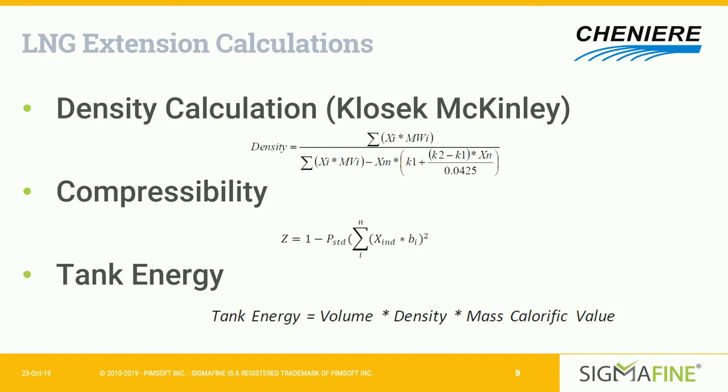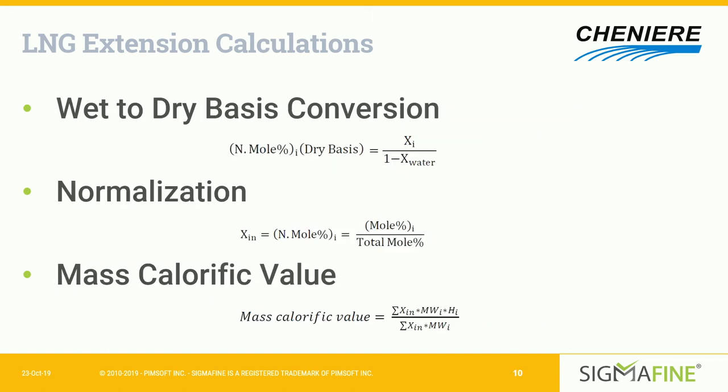The Klosek McKinley density calculation involves constants and K1 and K2 factors at different temperatures and compositions, along with molecular weight and compressibility. It lets us calculate our tank energy based on volume, density, and mass calorific value. These equations, built into the LNG extension, help us conduct our energy balance on a daily basis.